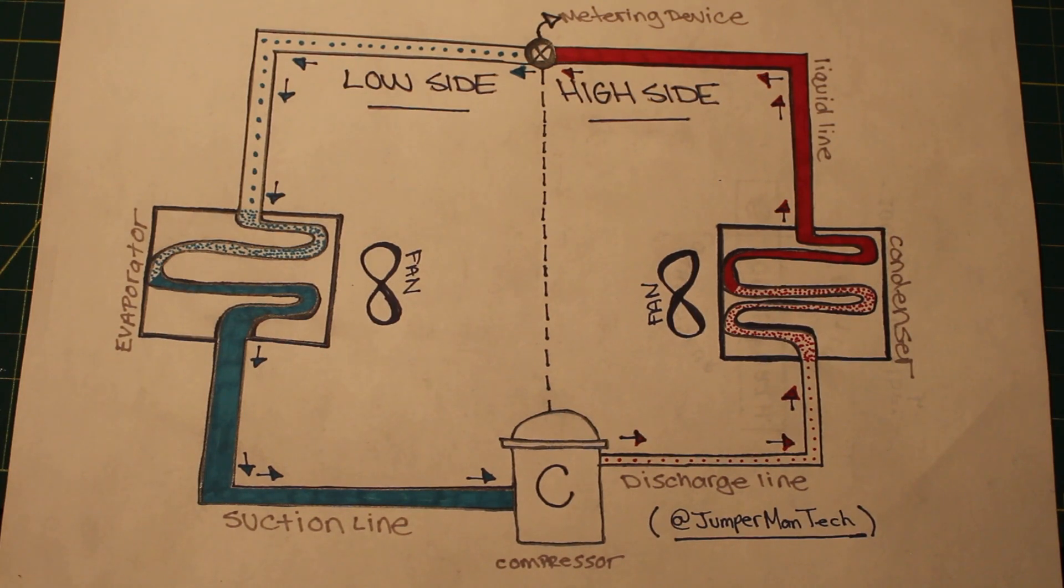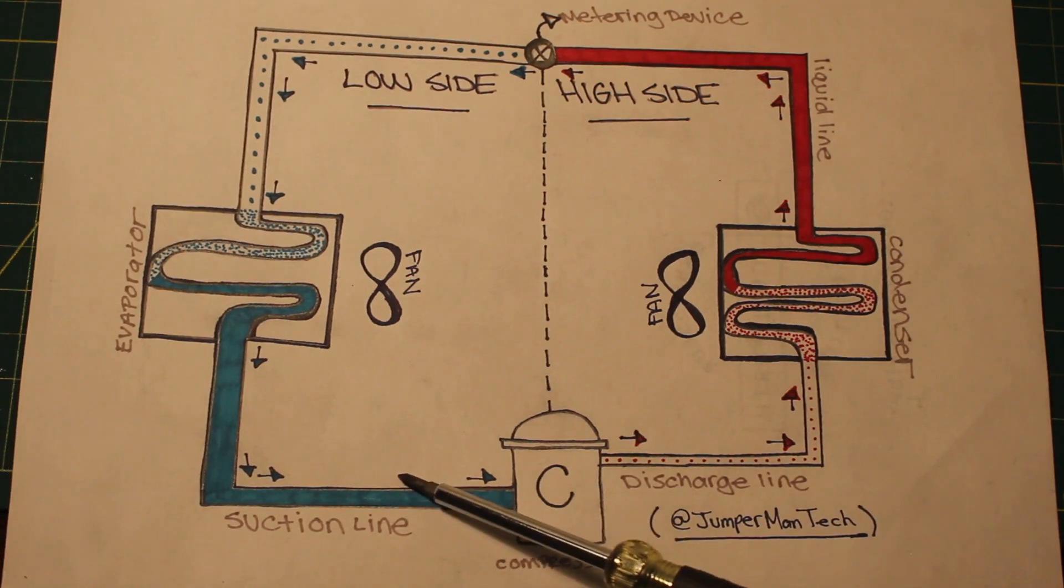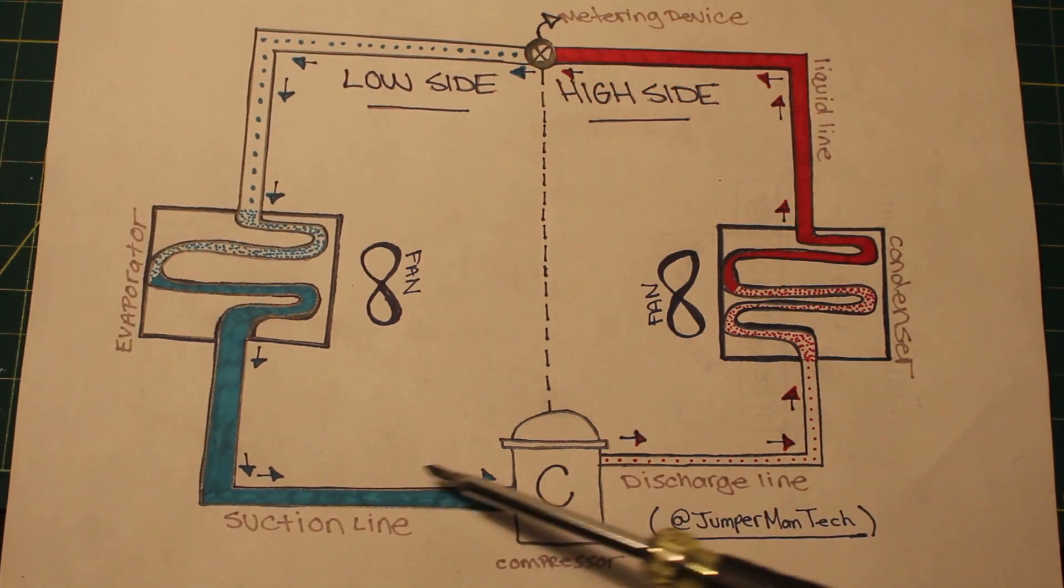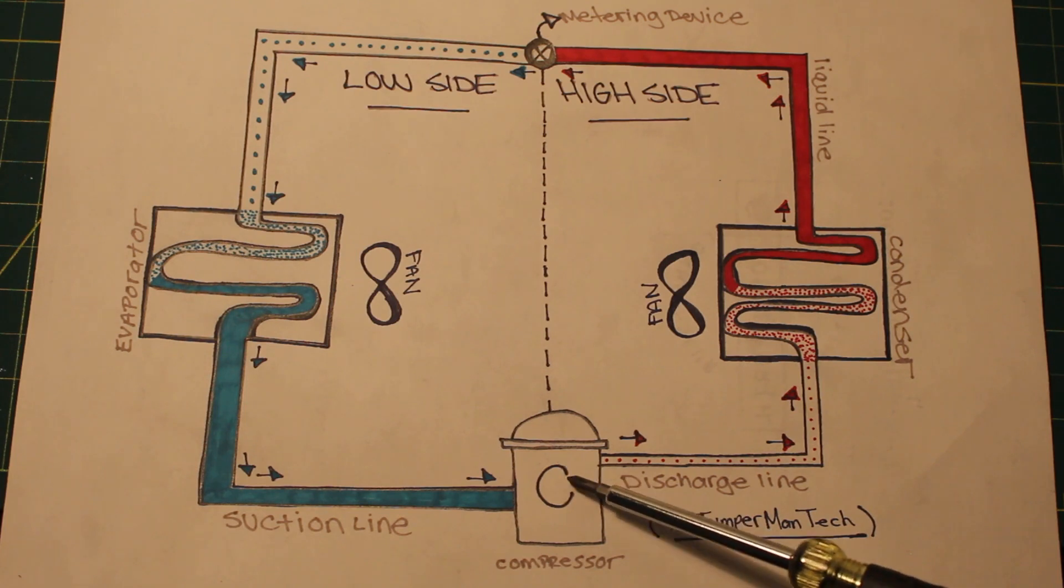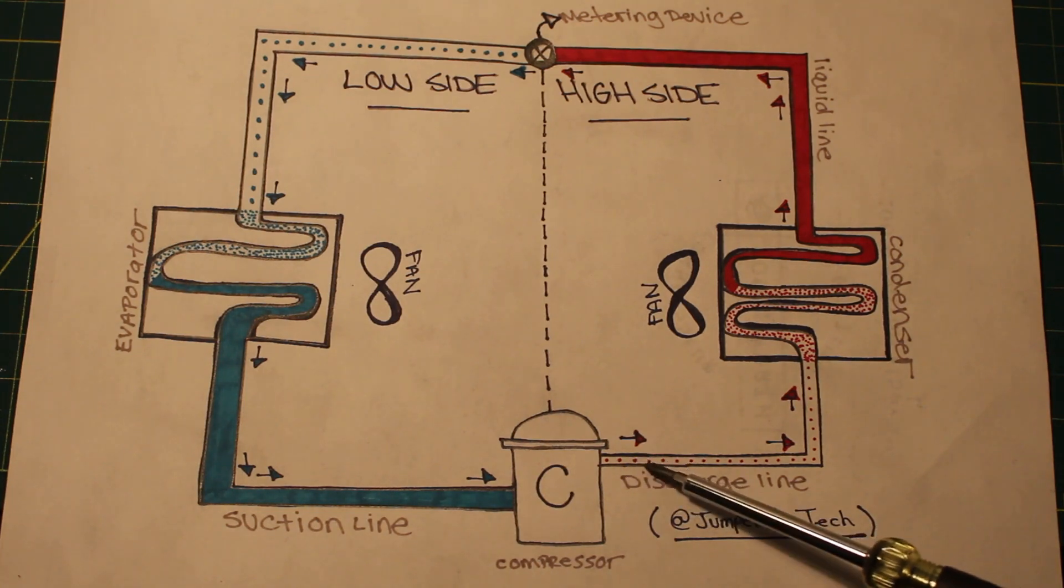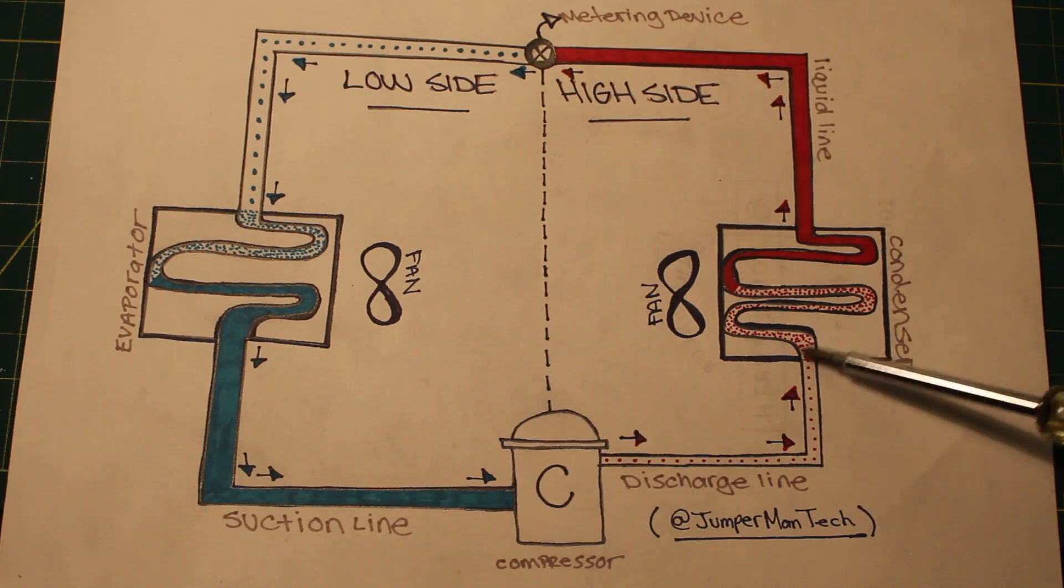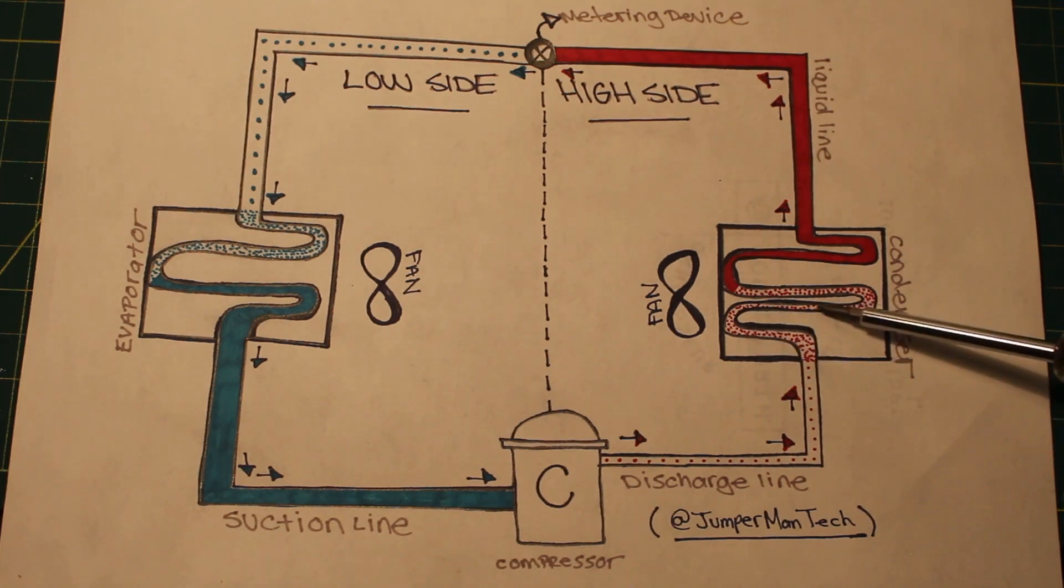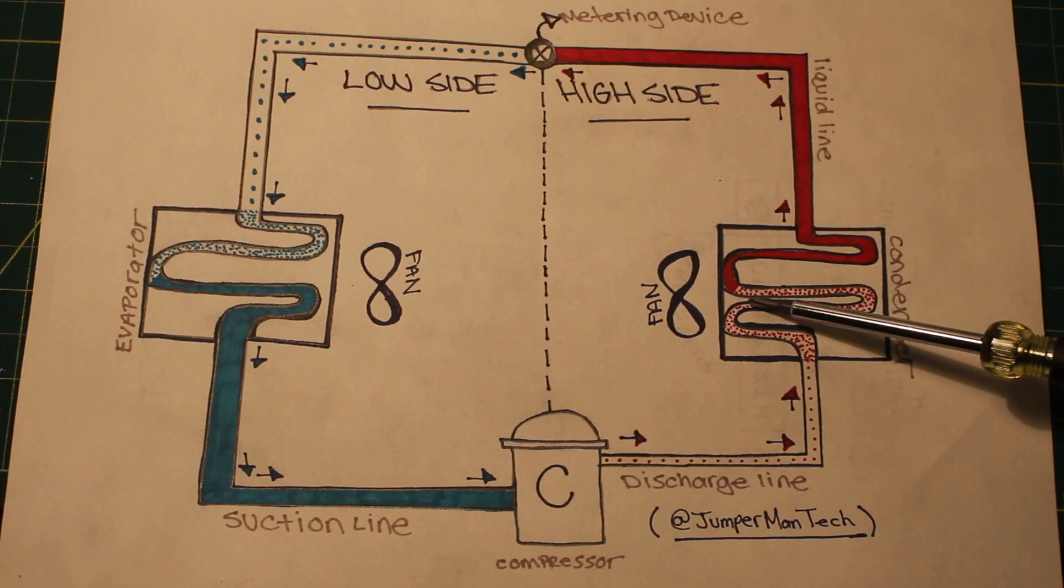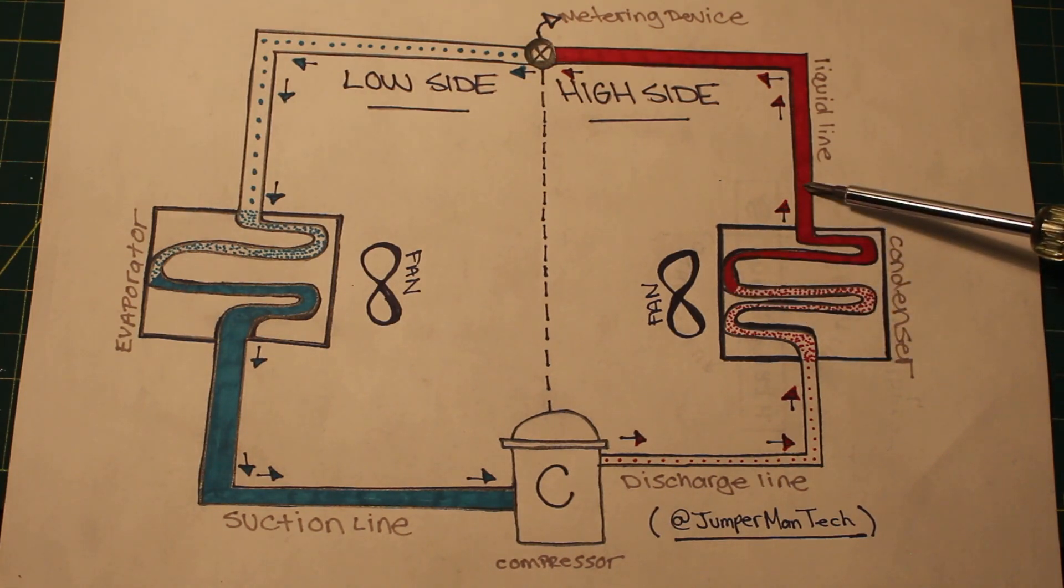Just to give you guys a quick recap: our refrigerant enters as a low pressure, low temperature, superheated vapor. It enters our compressor, compresses the refrigerant, and exits as a high temperature, high pressure vapor. It travels into our condenser where heat is being rejected. About midpoint, we fully condense. Now we exit through the liquid line as a high temperature, high pressure, sub-cooled liquid.